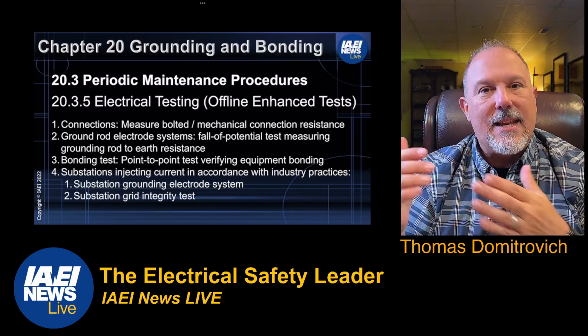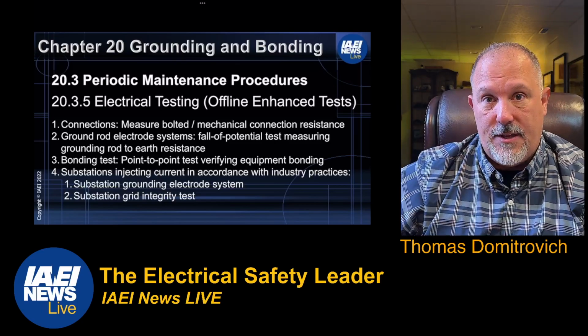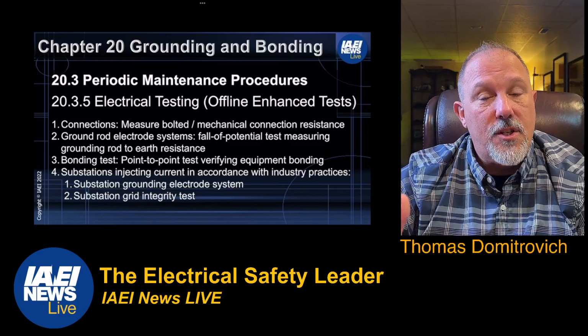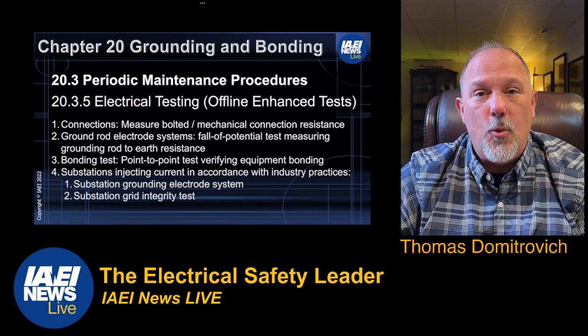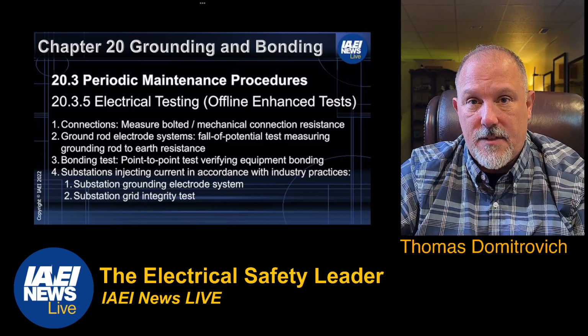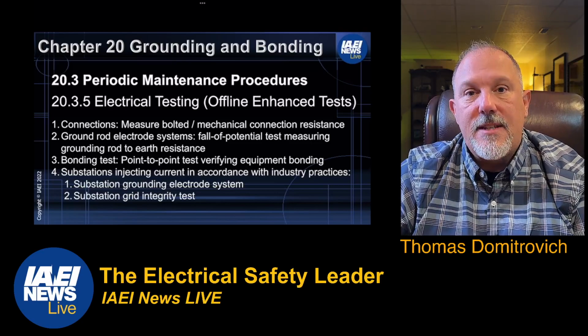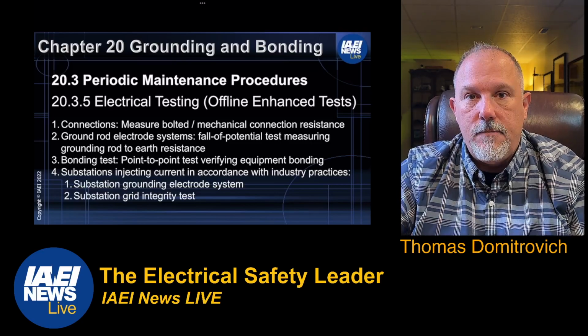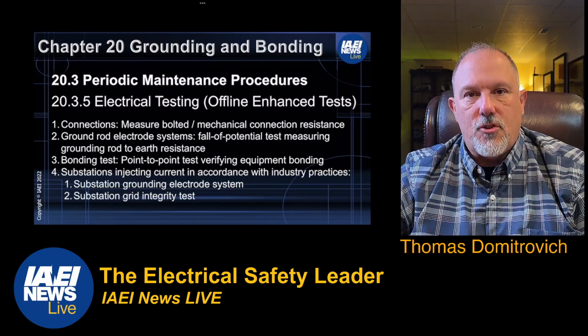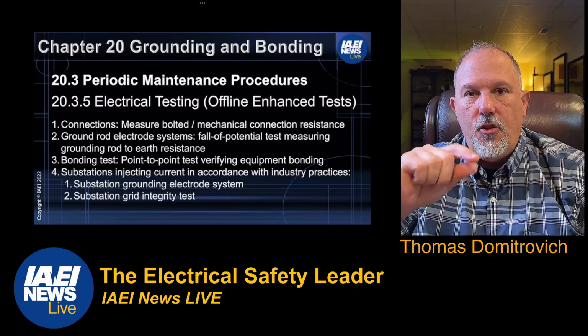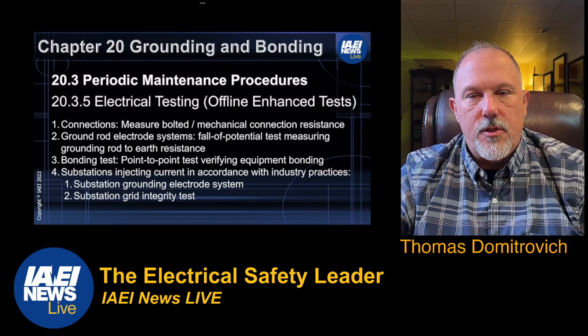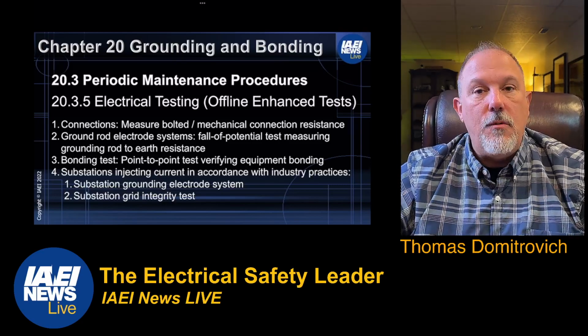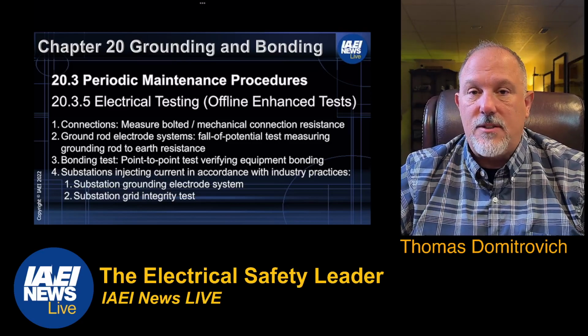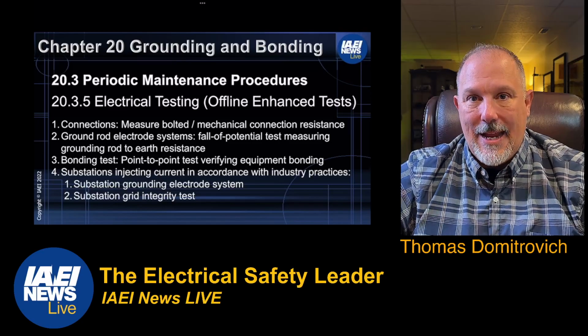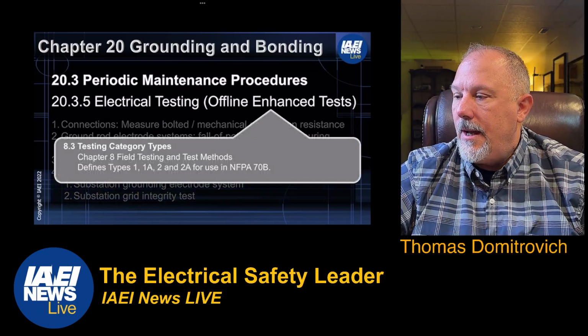So there are tests that can be performed. These are not standard tests. These are enhanced, which means you're questioning the integrity of something. It could be that the system saw a ground fault, and there were mechanical stresses placed on every component. You may elect, based upon that experience, to do these tests. They're not standard tests. This would be offline enhanced tests. And again, that is Chapter 8, 8.3.